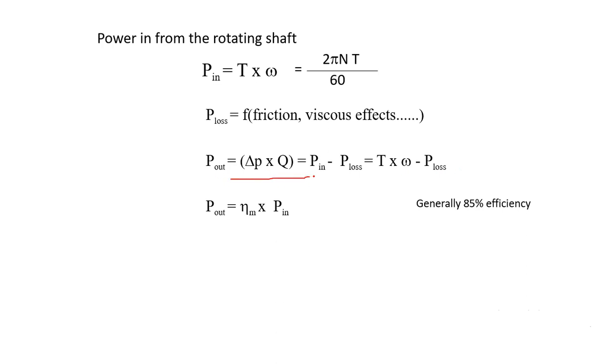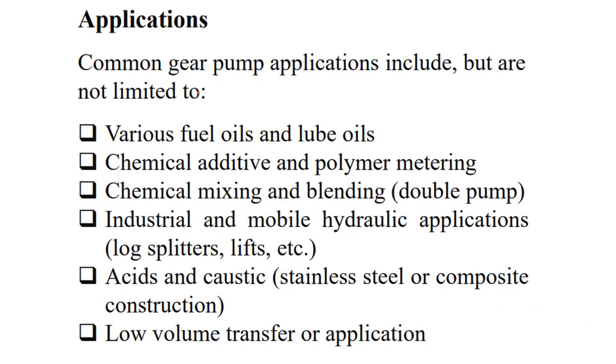We can calculate the power loss and power output as: Power_out = T × ω − P_loss. Knowing the power input, we can find the efficiency of the pump. Efficiency equals power output divided by power input, and generally we can achieve up to 85% efficiency for this kind of pump.